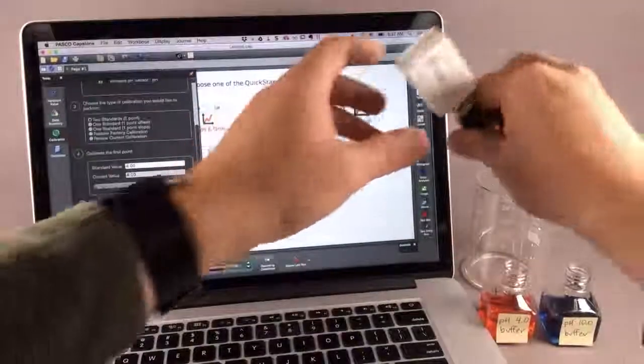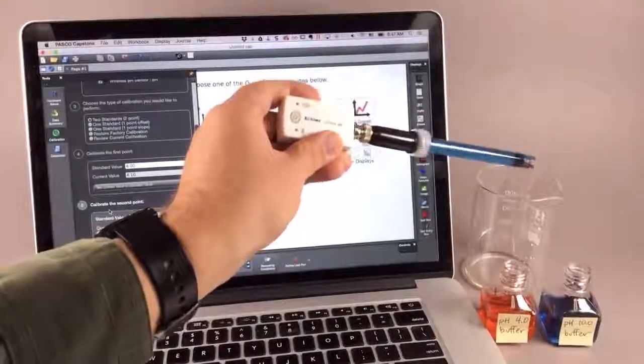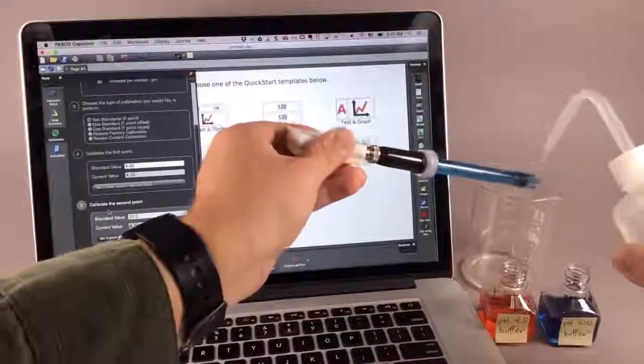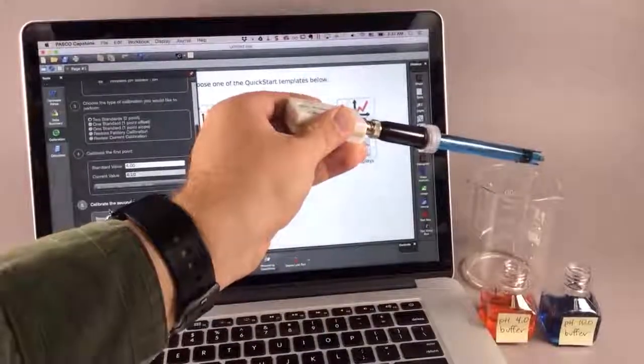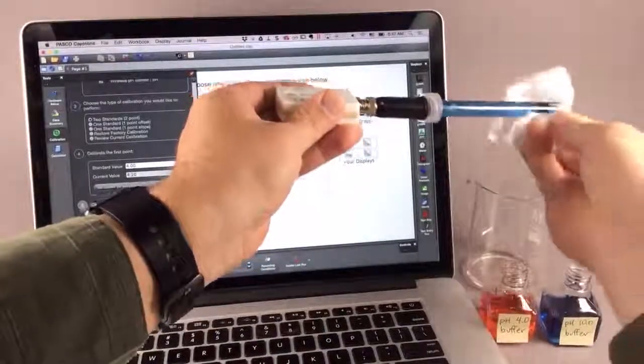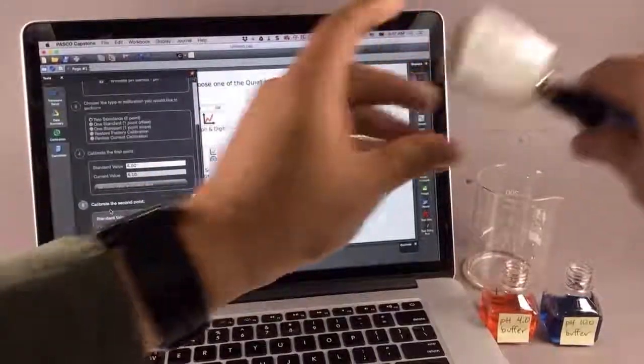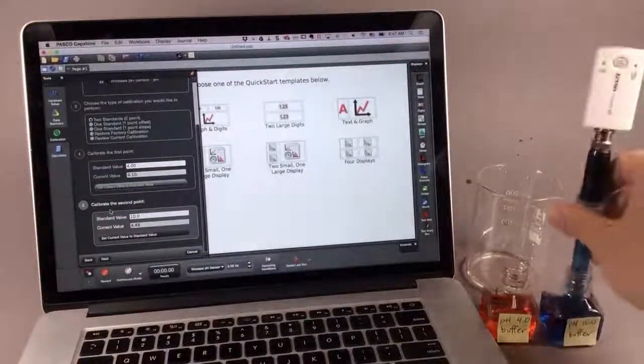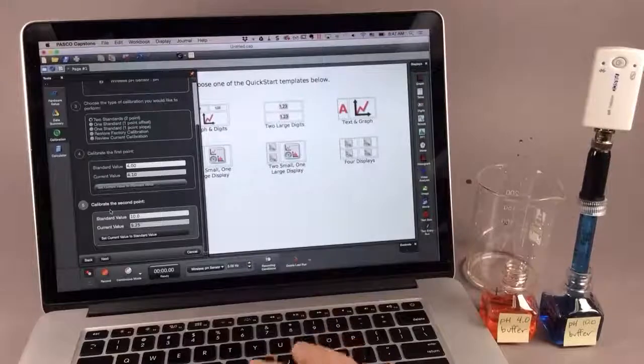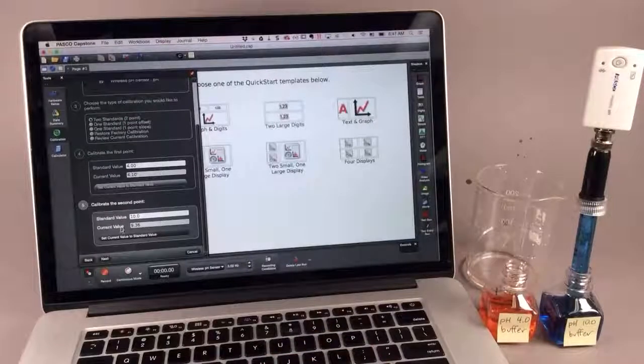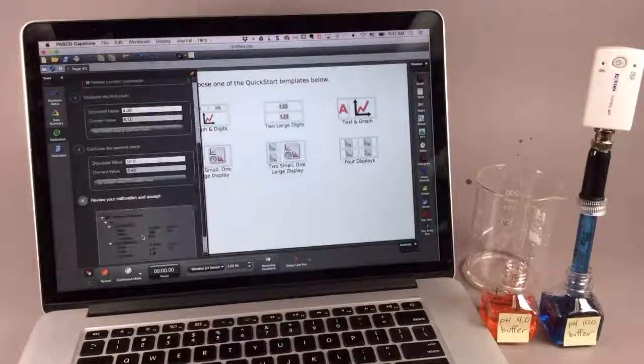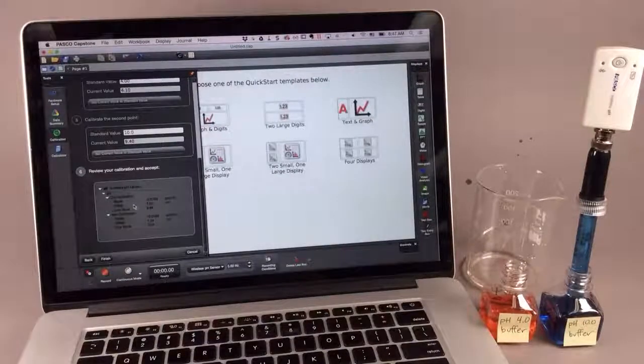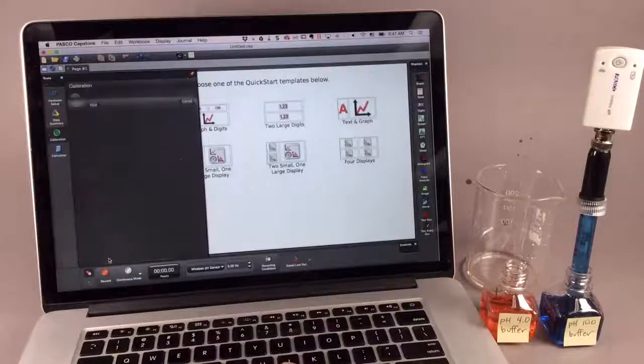So I will remove the sensor from the first calibration solution. I will rinse the sensor to make sure it's clean, gently blot it dry, and place it in the second solution. I'll observe the current value until it stabilizes, and once it's stable, I'll choose Set Current Value to Standard Value. It defines the calibration parameters for me, and I can press Finish.